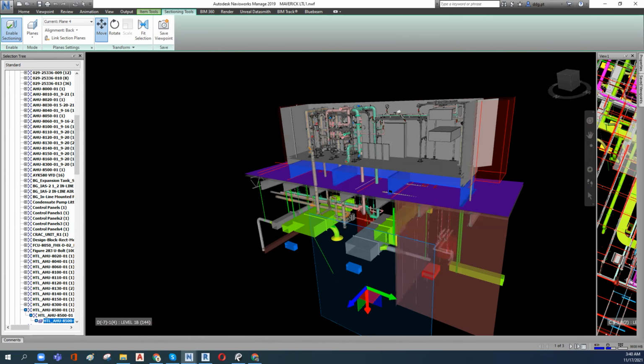Those aren't valves there, those are like vibration pads right there. As long as there's no valve that's going to impede the sensor or be able to valve off the chiller barrel, that up in that green line would probably be our best bet. Okay, so that'd be on the return, so that's fine.